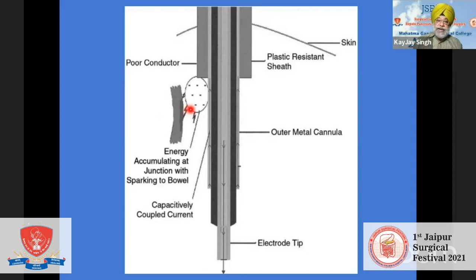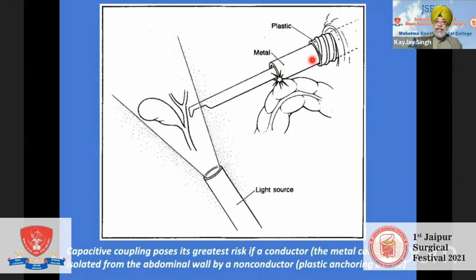This is the capacitive coupling, which is important. You see, there is no direct contact of this tip with any viscera, but there's a current buildup here between the metal and the plastic area, which damages any viscera coming in contact with it.